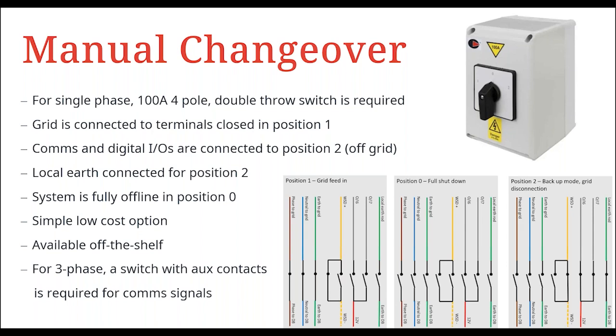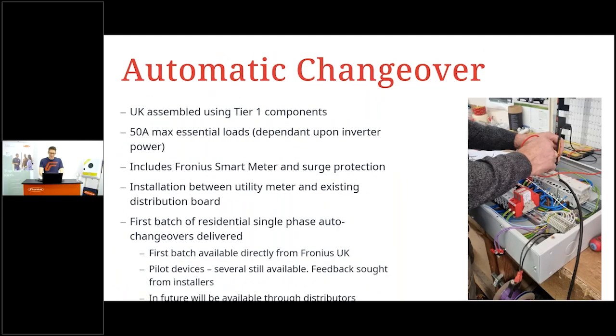The next option is something that we've been long waiting for. It's been taking some time to develop, and that is our automatic changeover solution. Because of the UK's wiring regulations, we have had to look at sourcing our own device for the UK and Ireland. We couldn't depend on the European devices, which again were designed for TT networks. So we've been working with Westminster Controls, who are a UK controls company, and we've now developed a solution both for single phase and for 3-phase.